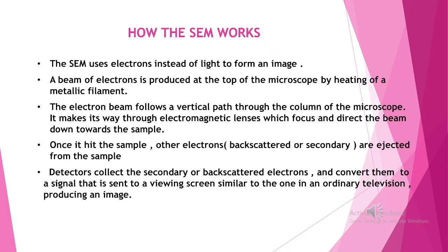Let's see how the SEM works. In a SEM, an electron beam is emitted from an electron gun, then narrowed to a size of approximately 0.4 to 5 nm in diameter through the use of one or two condenser lenses. The beam then passes through a pair of deflection coils in the electron column to deflect the beam in the x- and y-axis before interacting with the sample. This deflection ensures that the scan is done in a raster fashion, meaning each rectangular image captures a pattern of the sample. When the electron beam interacts with the sample, it loses energy through scattering and absorption by the sample.